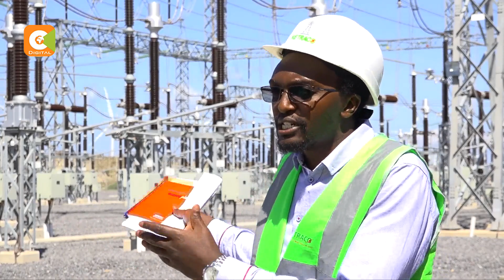So engineer, at the end of the day, this transmission line evacuating electricity, what does it mean for the country? This transmission line is capable of transmitting nearly 1,200 megawatts. What we are generating here with this wind farm is 310 megawatts maximum. So this line is not only meant for this wind farm. Should there be other generation sources planned along the transmission line towards Suswa, we will be able to connect these new plants to this line and evacuate that 1,200 megawatts comfortably into the grid.